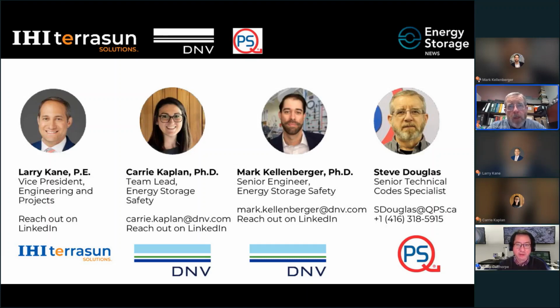The NFPA 855, when it was produced, was intentionally intended for use in the United States. There wasn't content addressing differences between the US and Canada as far as codes and standards are concerned. For example, the definition of a dwelling unit is different in the US than in Canada. Those sorts of things would need to be addressed in the NFPA 855 document. I think it would be good if 855 could be modified to include other countries like Canada, but until that happens, I think you'll have a hard time getting it adopted elsewhere unless it includes the national deviations for that country.